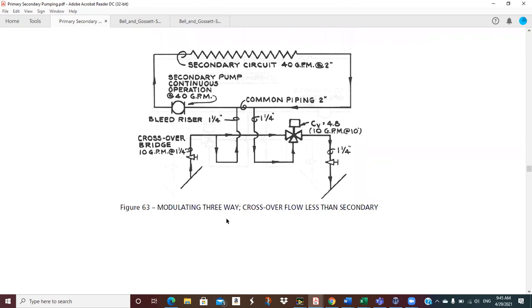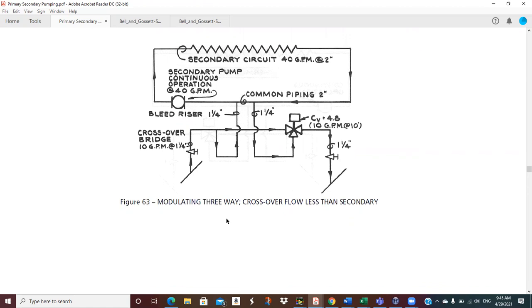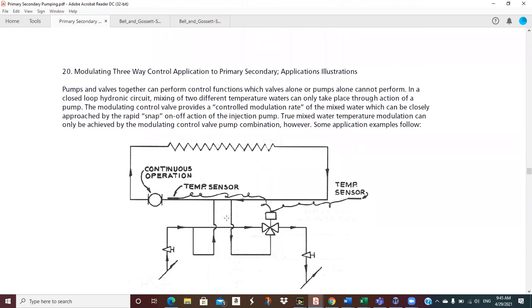from your valve supplier. And then this is the heating situation where we got 10 GPM in the crossover and 40 in the secondary. And so the CV now drops to 4.8. Again, you take 10 divided by 2.3, take the square root of it, and take that result and divide it into 10, your flow rate. CV comes out 4.8. So that's what you should size that valve for. Pretty good, pretty good.